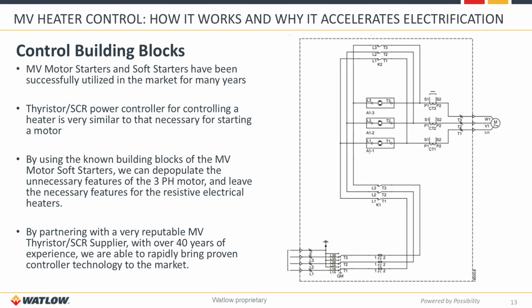I've got a diagram over here on the right-hand side that goes through and depicts exactly how a motor starter, soft starter works. You see this center thyristor stack. These are back-to-back thyristors that regulate the voltage over to the motor during the soft starting process. By using these known building blocks of the soft starters, we can manipulate that and transition that into an industrial heater controller within the system.